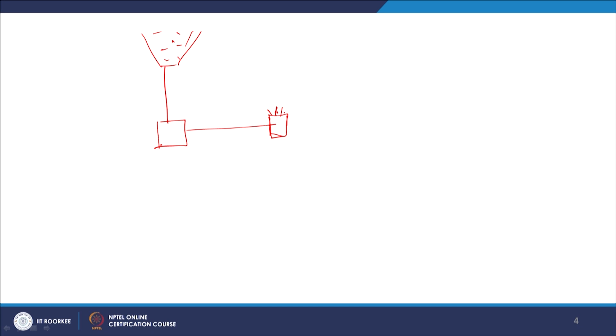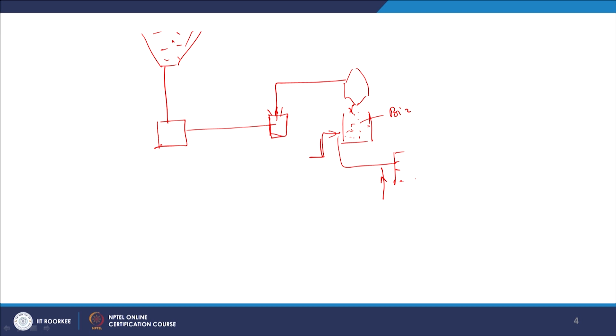After the cyclone separator, the pulverized coal is separated out and there is a bin in which it is collected, and in this bin a separate air supply arrangement is made, that is known as primary air. This air takes pulverized coal from the bin and it is supplied to the burner, right. This is a little different from the previous arrangement. Here also secondary air will be supplied near the burner, but the primary air is supplied when the fine particles of the coal are collected in the bin, right. And this system has a very good flexibility.